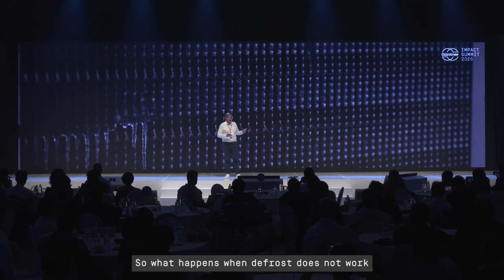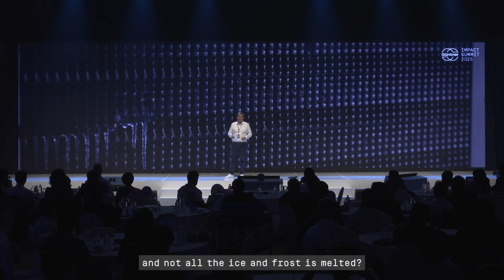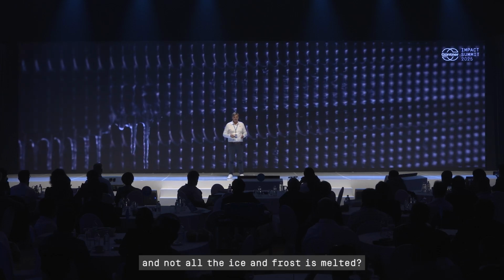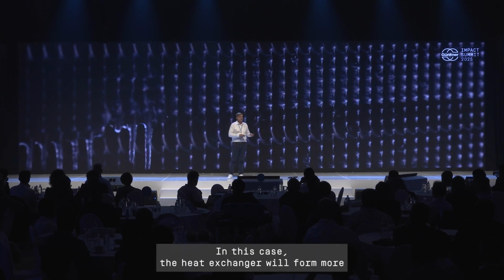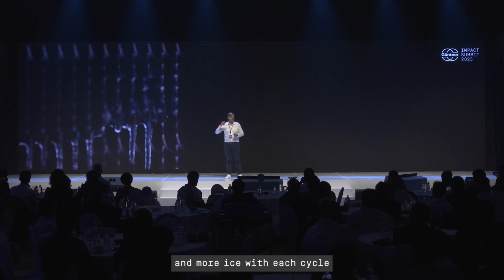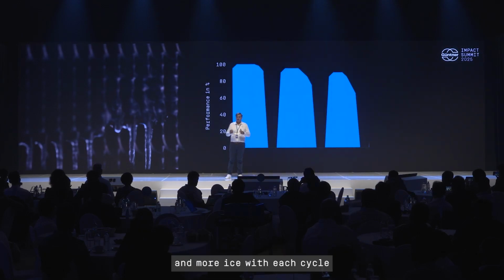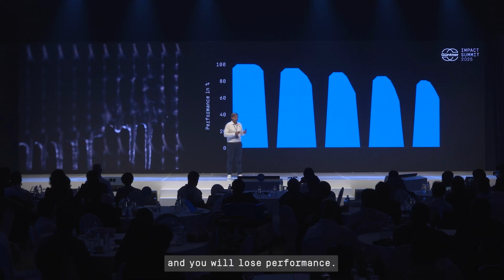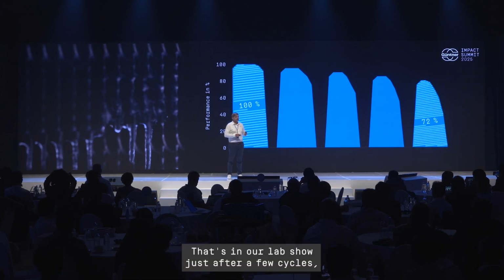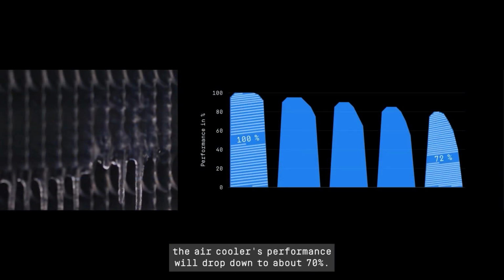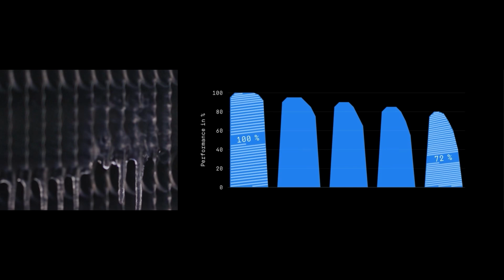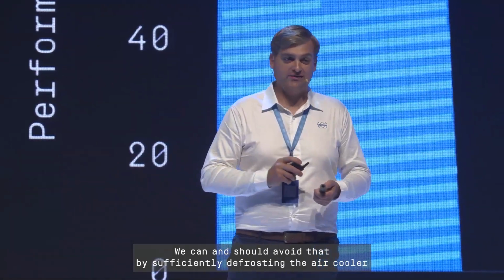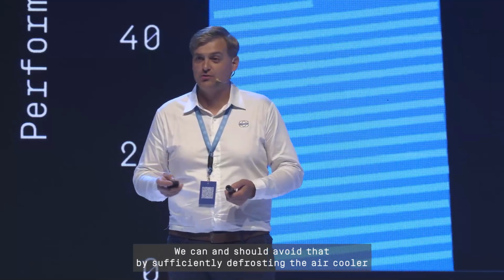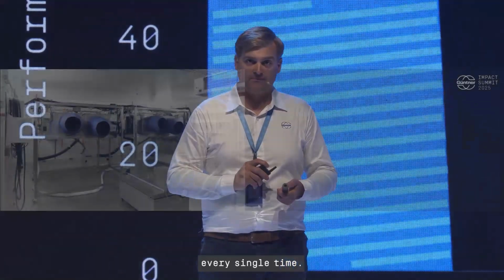So what happens when defrost does not work and not all the ice and frost is melted? In this case, the heat exchanger will form more and more ice with each cycle, and you will lose performance. Tests in our lab show that after just a few cycles, the air cooler's performance will drop down to about 70%. We can and should avoid that by sufficiently defrosting the air cooler every single time.